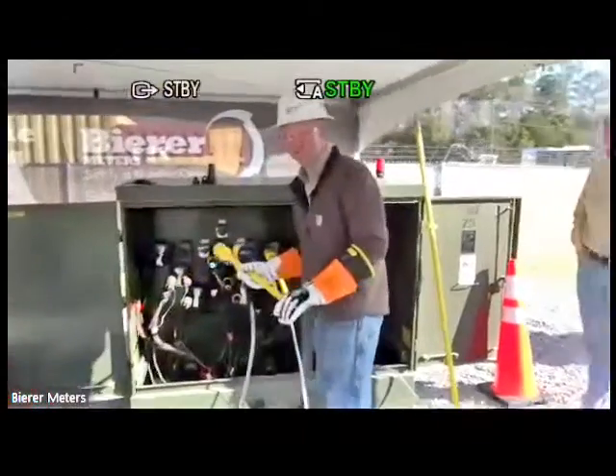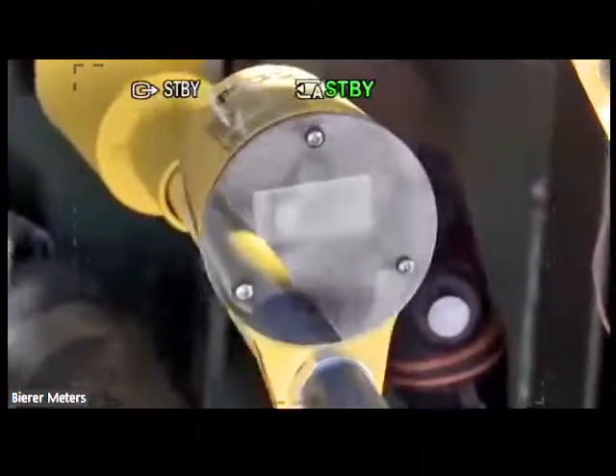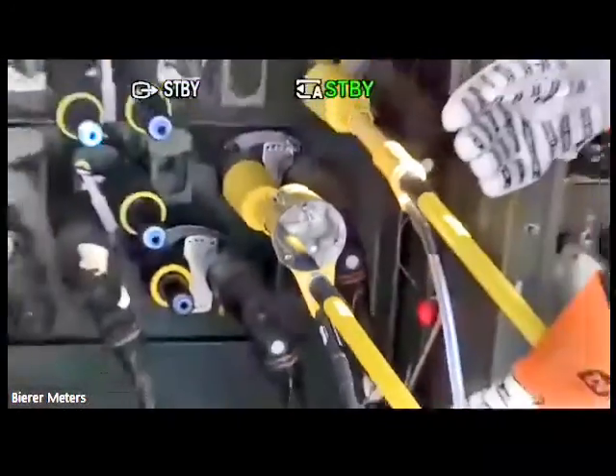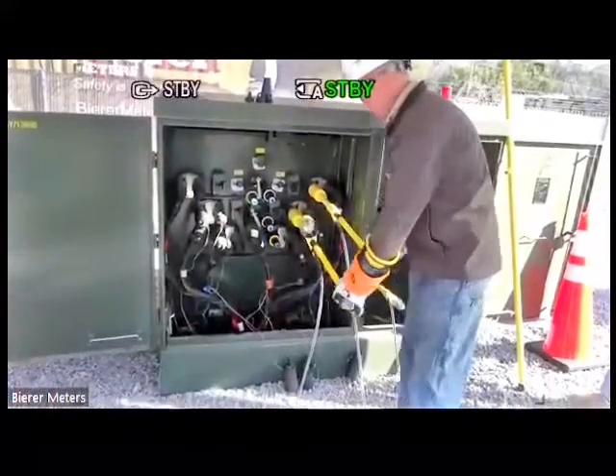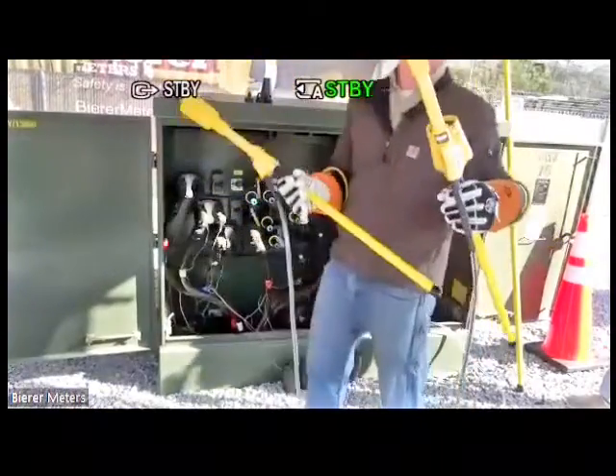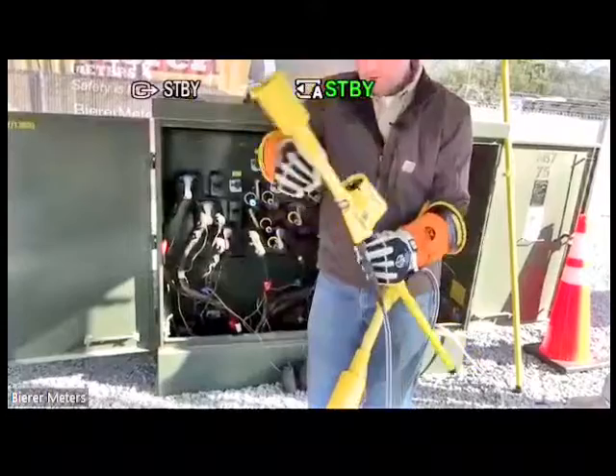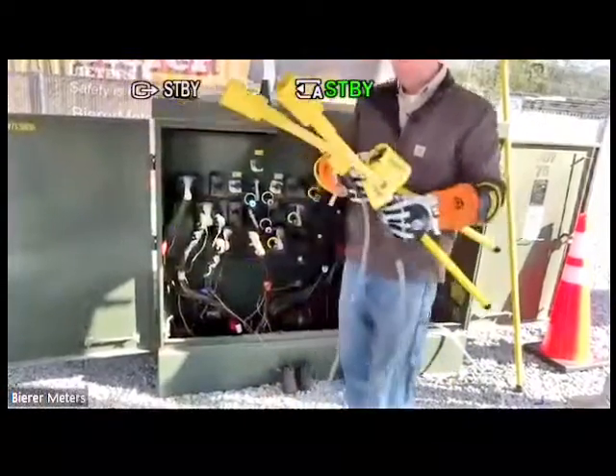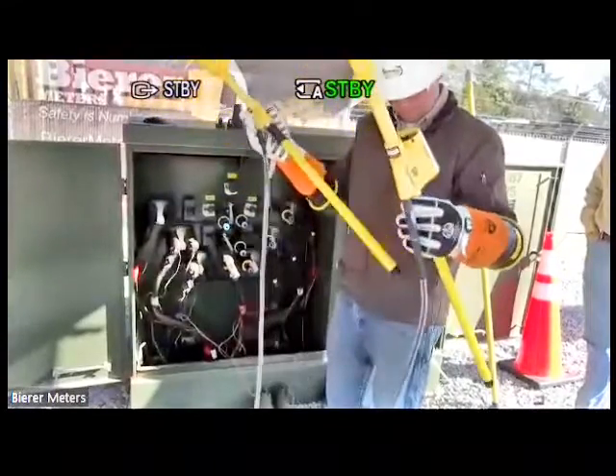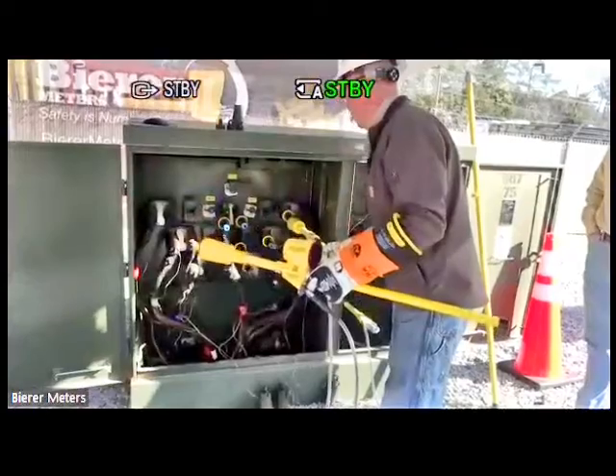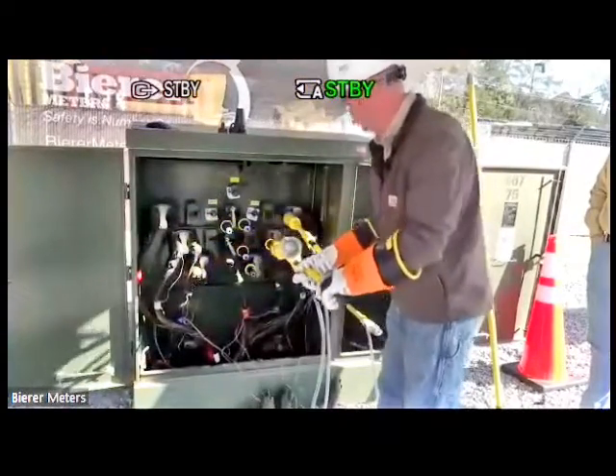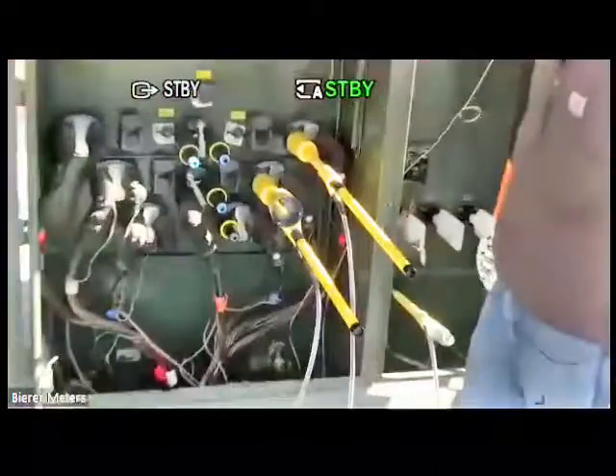Again, I'll just pick any two of the three. It doesn't matter which one it is. All right, so it just shows a 1, right? Okay, that's the display it'll give you if the screen is overloaded. In other words, it's just out of range. It's just going to show you a 1 if it's out of range. All right, so that's all it's going to do. So I want to flip this to the 20 kV switch position, and let's see what it does in that switch position. Remember what this is: phase to ground and phase to phase. Okay, so that's 13,900 roughly.